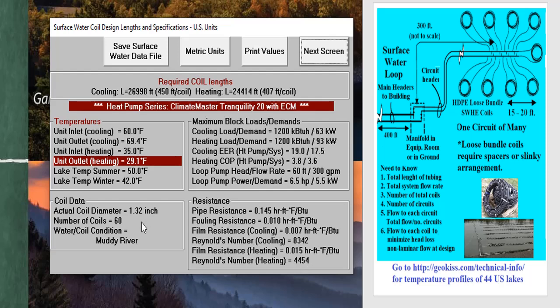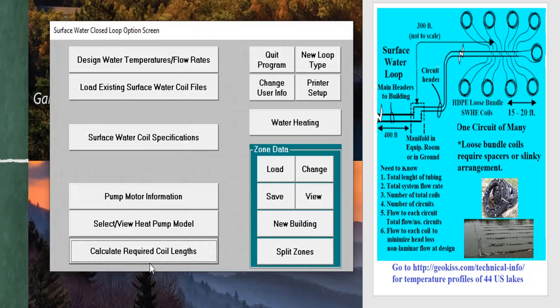And now what we have is 500 foot of 1-inch tubing, and we're still pumping 5 gallons a minute through it. Okay, so let's look at that number. Your antifreeze salesman may say, oh, you need 30%. So let's see what happens if we listen to that antifreeze salesman.